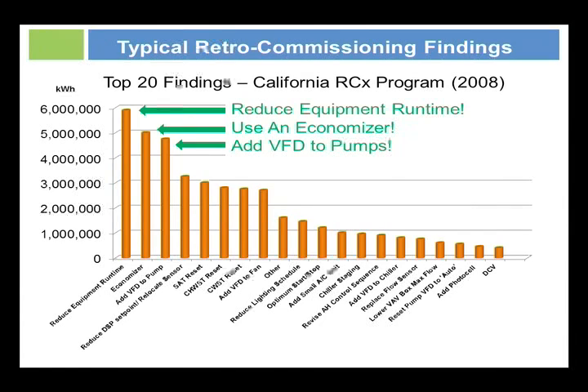Can I leave a sensor out in the space so that if it gets too cold or too hot, go ahead and start the unit back up, but let the unit only run for an hour or two before school starts and an hour or two after school is done. And then if it drifts too far from set point at night, in the summer or winter, it'll start the unit. But otherwise, leave the unit off and save the energy.